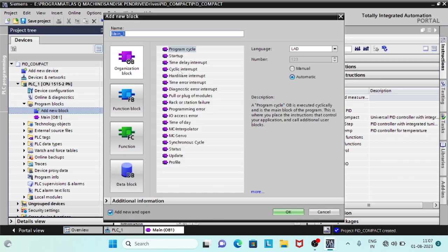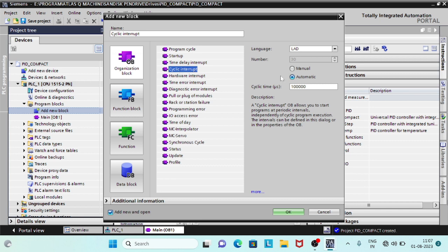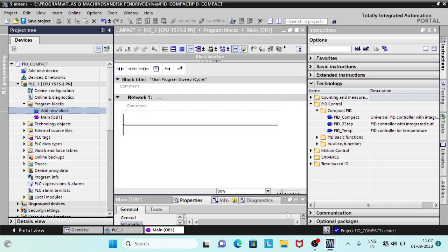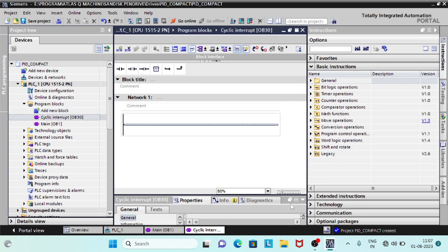The call of the PID Compact takes place in the cyclic interrupt OB, since the discrete software controls must be called at a defined time interval.